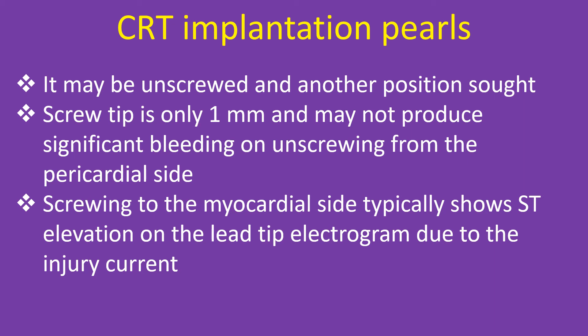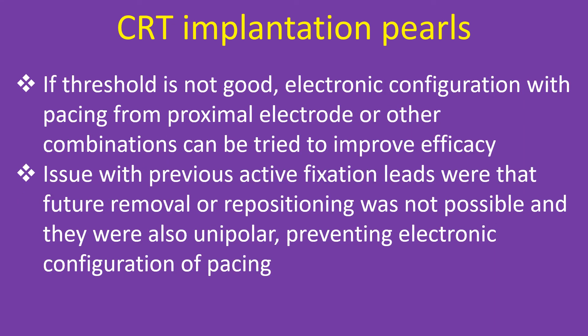Screwing to the myocardial side typically shows ST elevation on the lead tip electrogram due to the injury current. If threshold is not good, electronic configuration with pacing from the proximal electrode or other combinations can be tried to improve efficacy. An issue with previous active fixation leads was that future removal or repositioning was not possible and they were also unipolar, preventing electronic configuration of pacing.